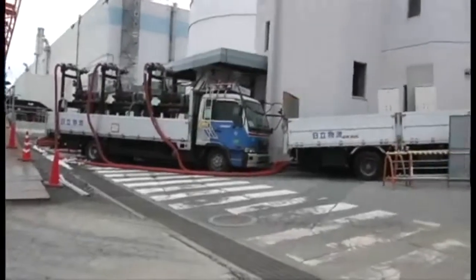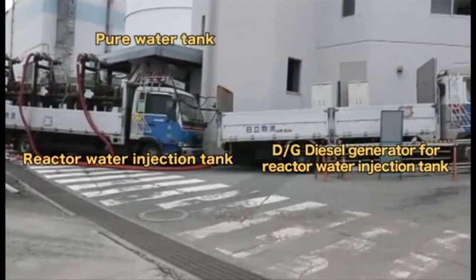In a worst-case scenario, if these pumps malfunction, we have installed a reactor injection pump and another purified water tank using a different route. This is installed next to the turbine building. There are 2 2,000-ton tanks. Next to the tanks, there are reactor injection pumps and a diesel generator for exclusive use. As such, we have prepared the pumps from a thorough safety perspective. There are 3 reactor injection pumps next to the purified water tank.